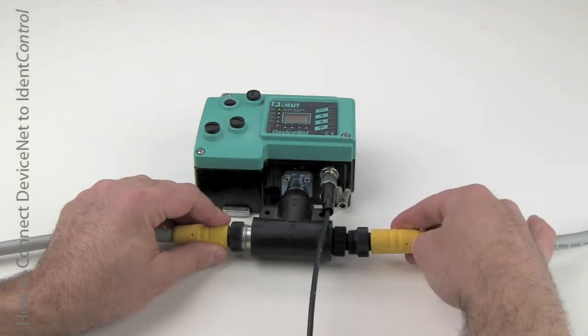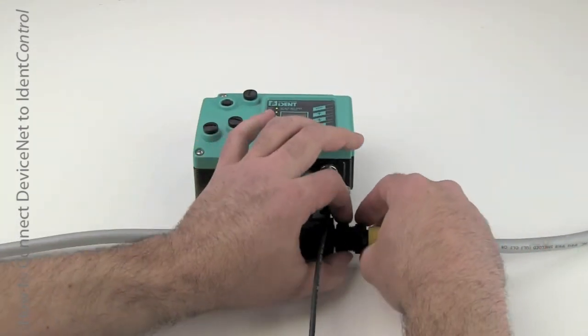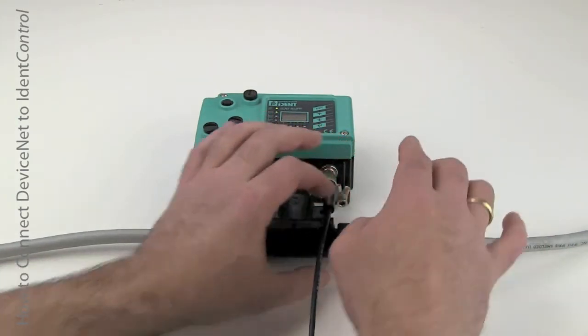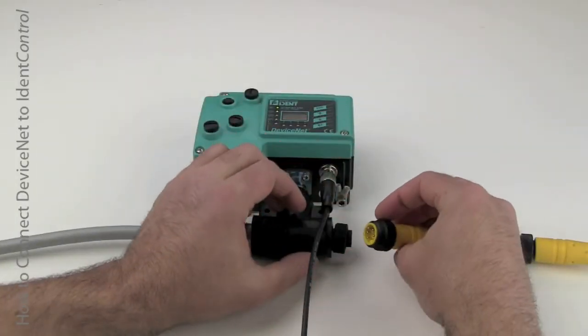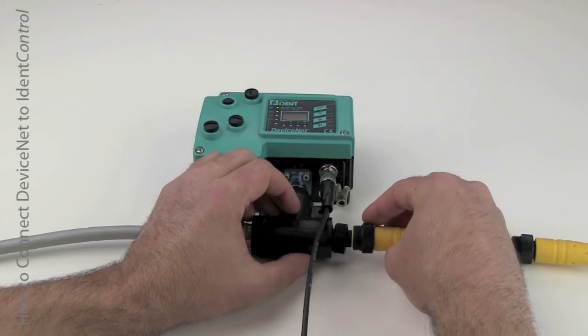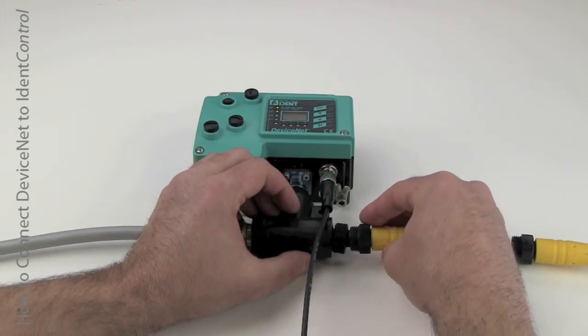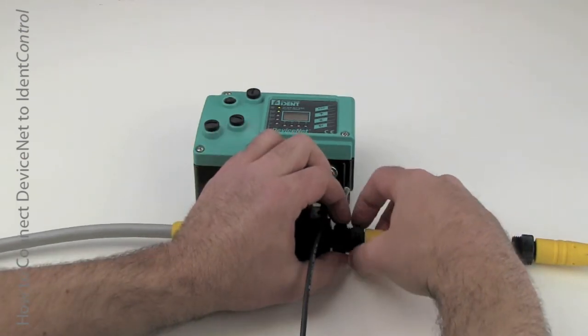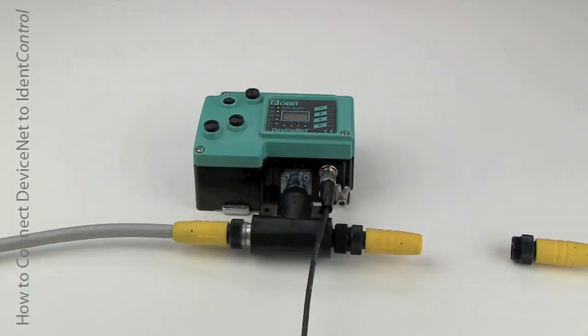If this happens to be the last node on the DeviceNet network, make sure the DeviceNet out connection gets replaced by a terminator. There should only be two terminators on the DeviceNet network. One at the last node on the trunk, and then one back at the beginning.